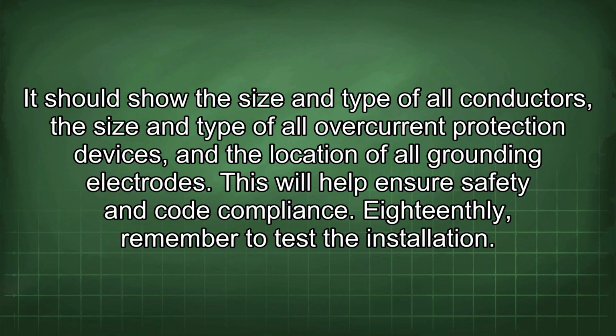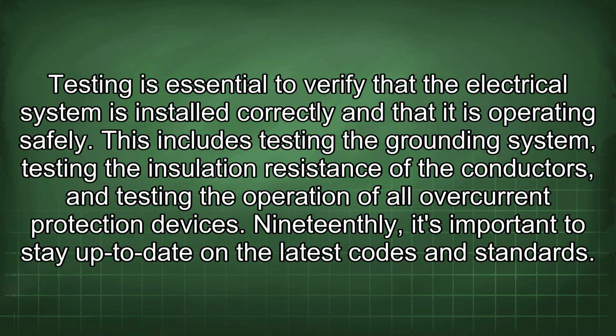18thly, remember to test the installation. Testing is essential to verify that the electrical system is installed correctly and that it is operating safely. This includes testing the grounding system, testing the insulation resistance of the conductors, and testing the operation of all overcurrent protection devices. 19thly, it's important to stay up to date on the latest codes and standards.